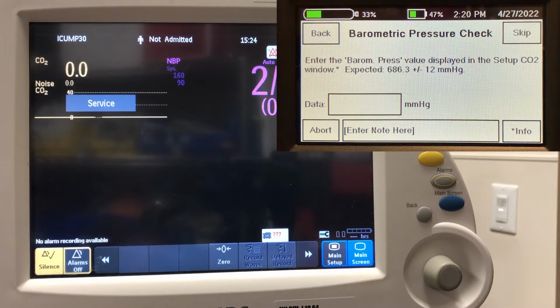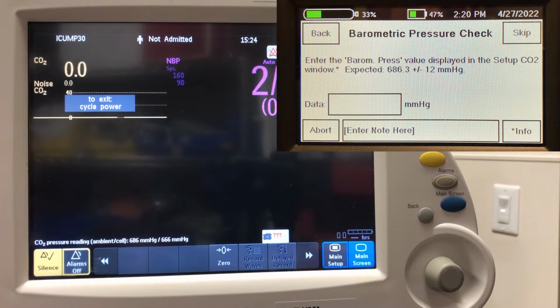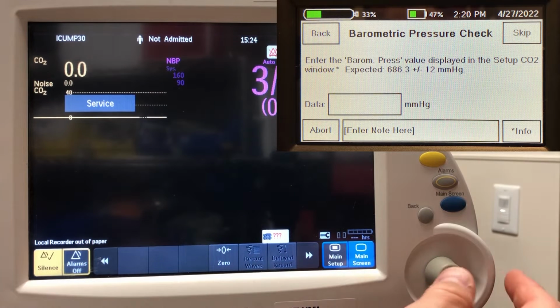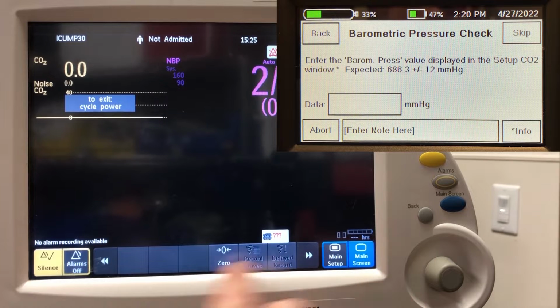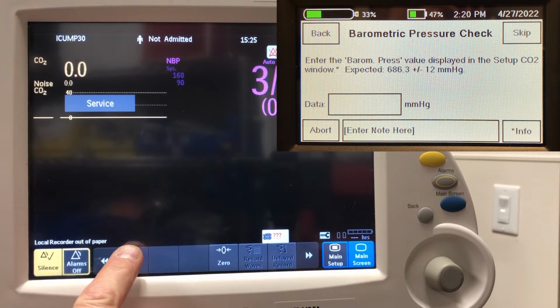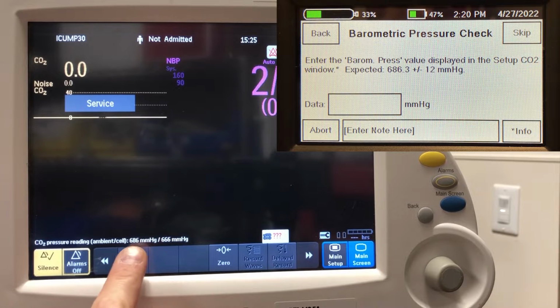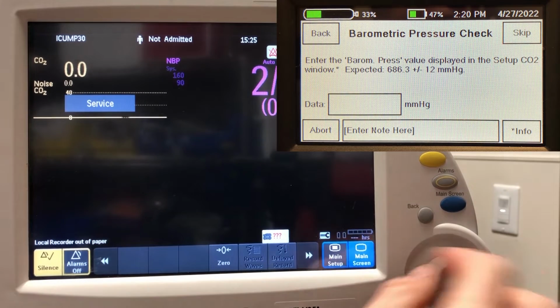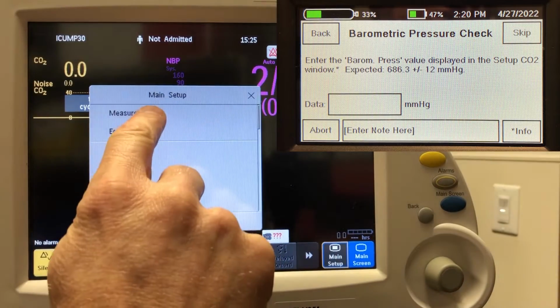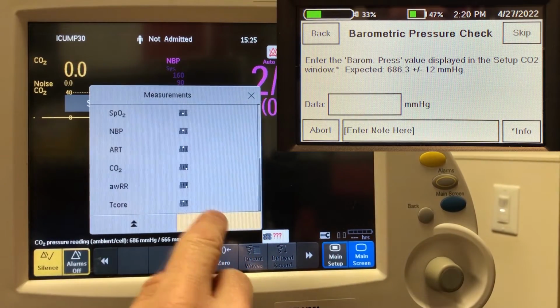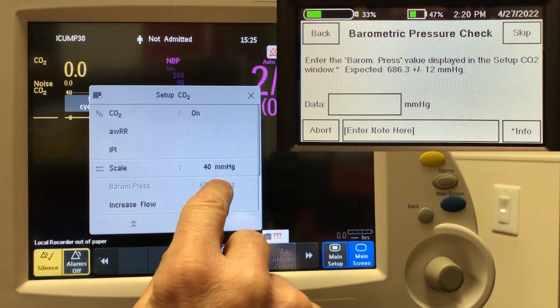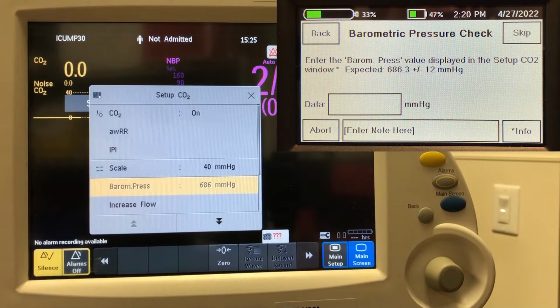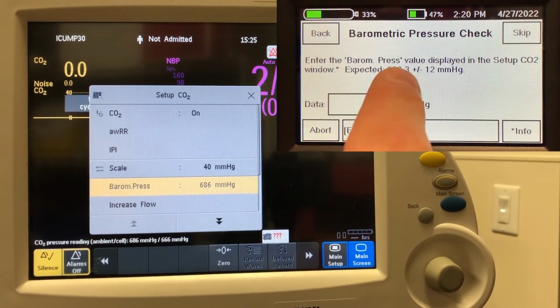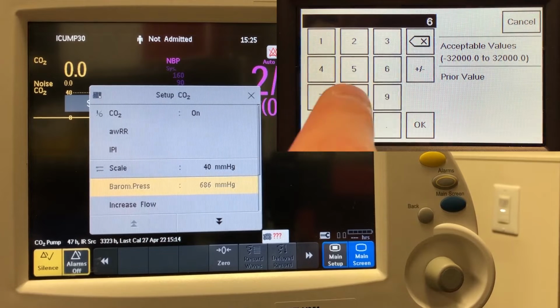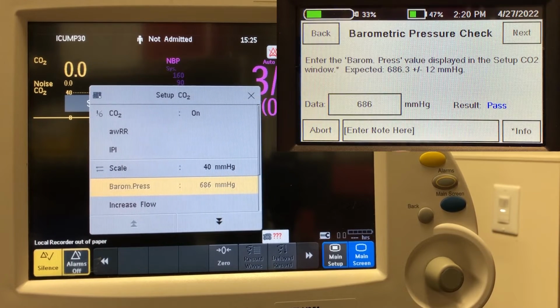Expected value is 686.3. We look right here. So we can see that in a couple places. This scrolling message shows it. It's the first of the two values. 686 is what it's reading right there. Or I can go into the main screen, go into measurements, down to CO2. And it shows it right there as well, 686 millimeters of mercury. So that's almost exactly what the Smart Tank's internal barometer is reading.